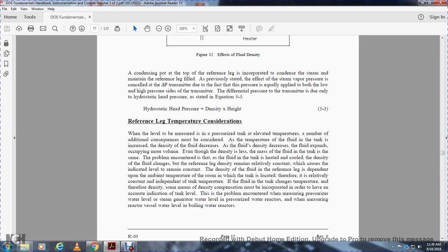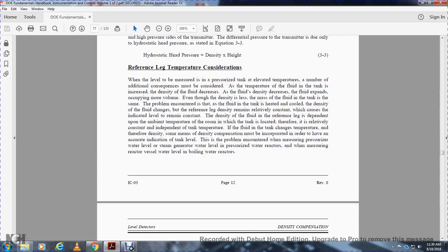The density of the fluid in the reference leg depends on the ambient temperature of the room in which the tank is located, and is therefore relatively constant, independent of the tank temperature. Some means of density compensation must be incorporated in order to have an accurate indication of the tank level. This problem is encountered when measuring pressurizer water level and steam generator water level in pressurized water reactors, and when measuring reactor vessel water level in boiling water reactors.